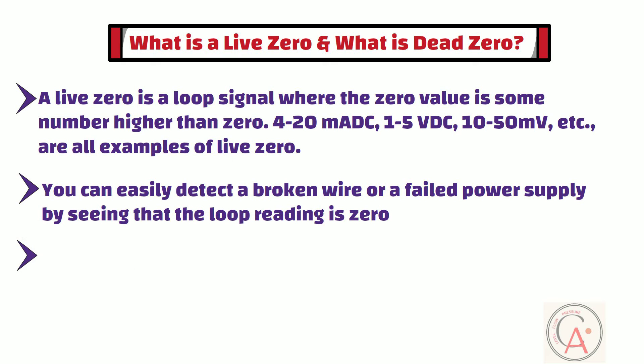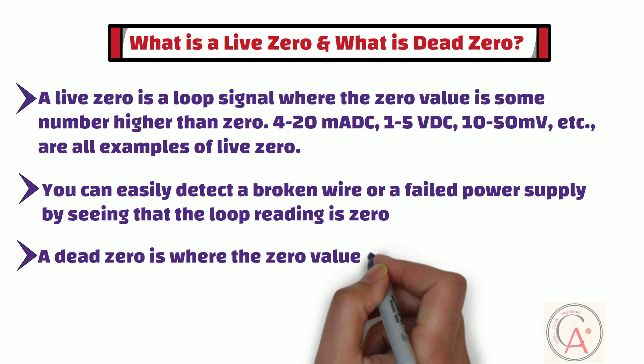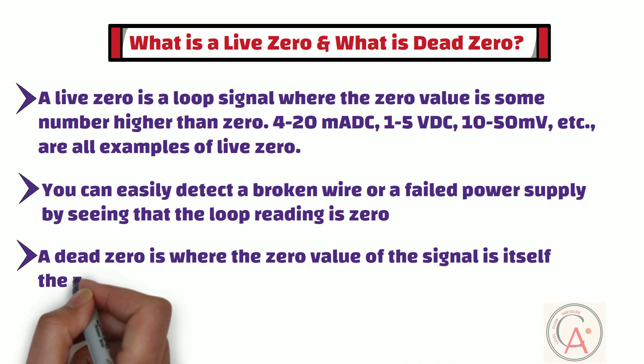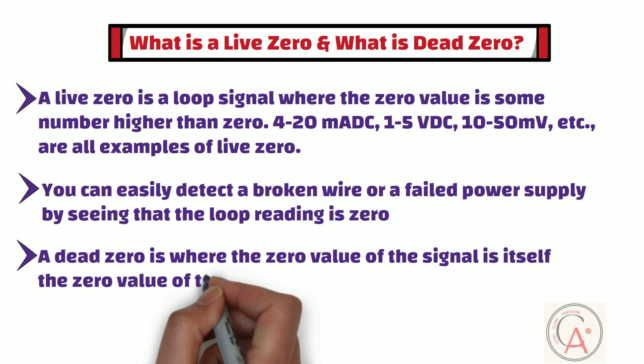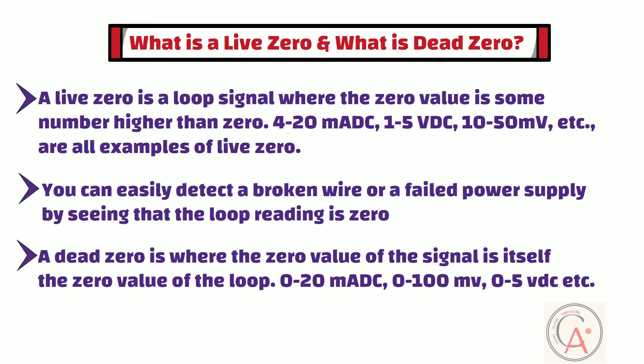On the other side, a dead zero is where the zero value of the signal is itself the zero value of the loop. 0-20mA DC, 0-100mV, and 0-5V DC are all examples of dead zero. In this type of signal, we cannot distinguish between a connection break signal and a zero signal — in both cases, the value will be zero.